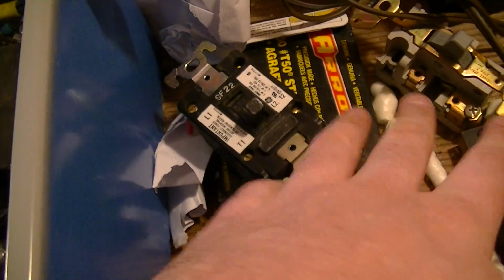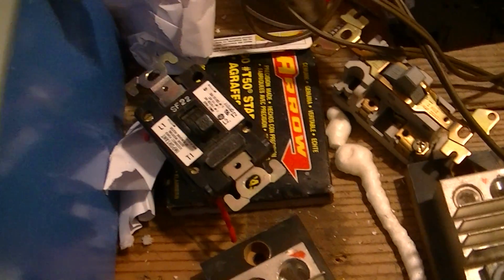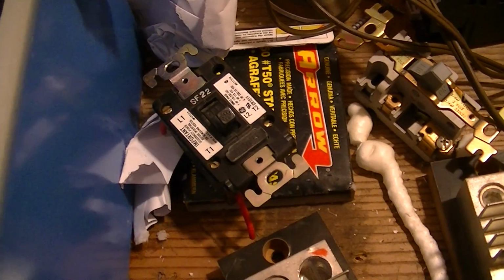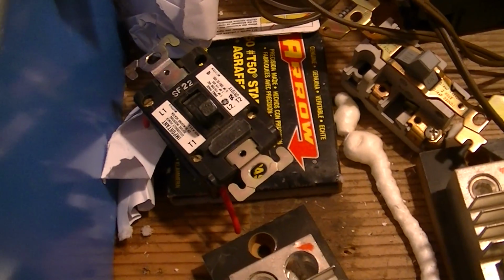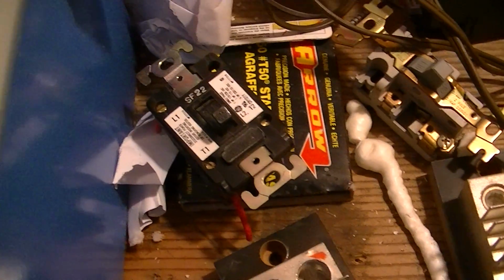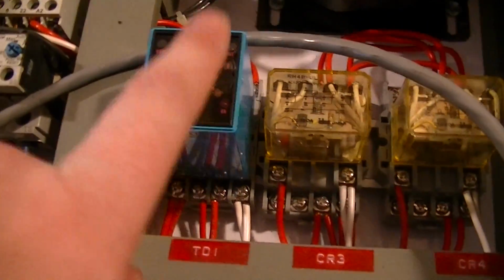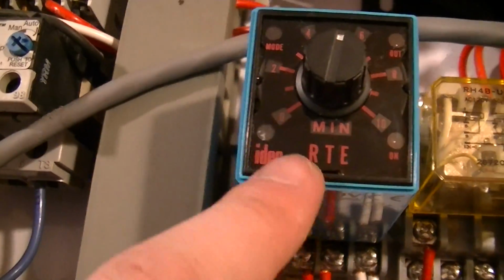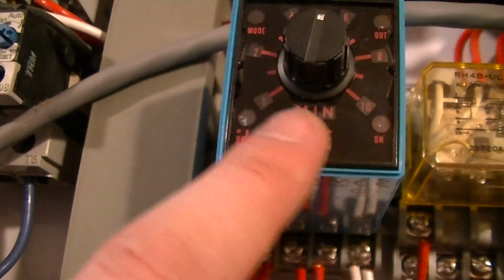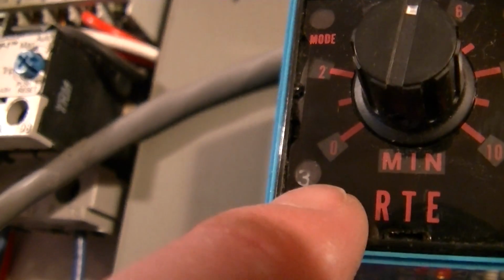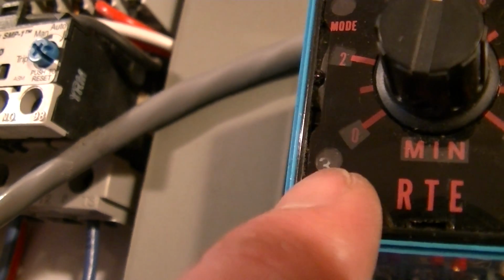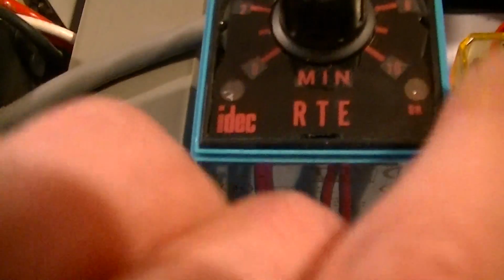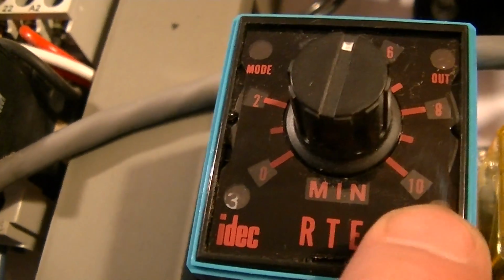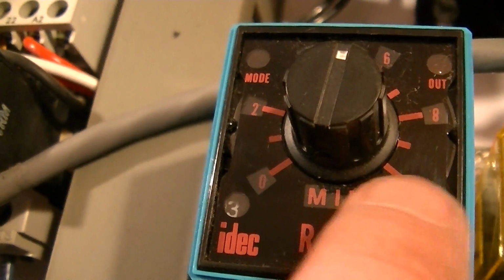That's the difference, because it's very common for these things to have their own obscure things, like the motor starter heaters, partly to ensure compatibility, partly because industrial control schmo, getting more money. Also, delay relay, these are quite useful. This isn't one of the really fancy ones. While it's adjustable for a whole range of different settings, you have to tell the relay what the legend is set to. The little thumb wheel, in this case it's set to number 3, and there's a little legend on the side of it.